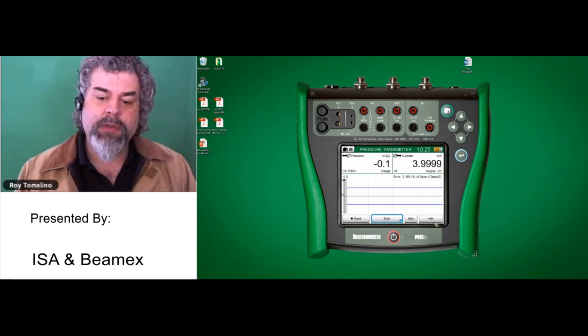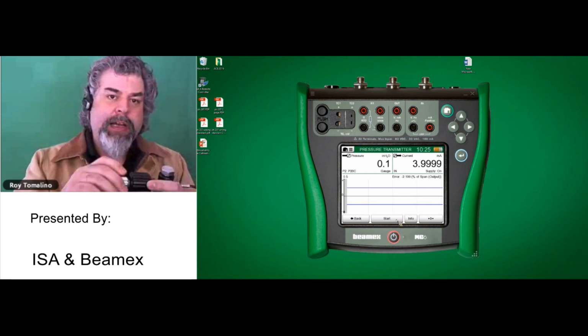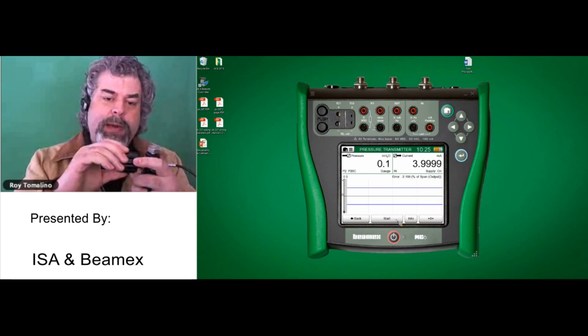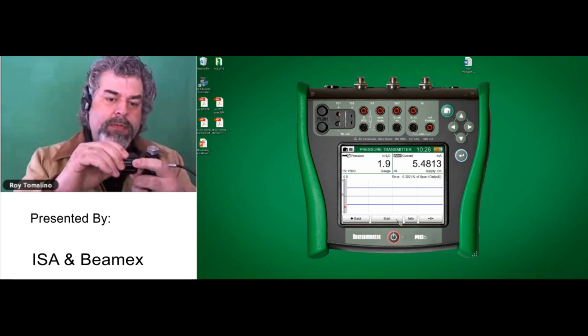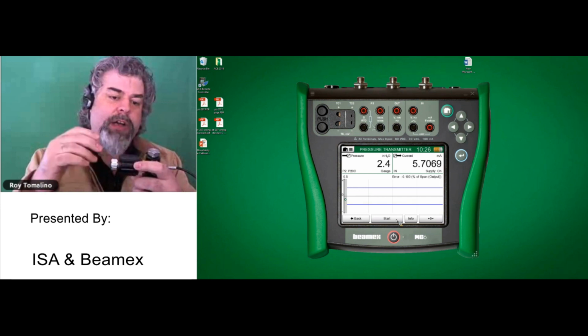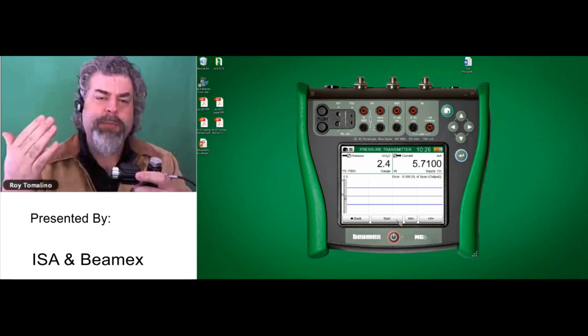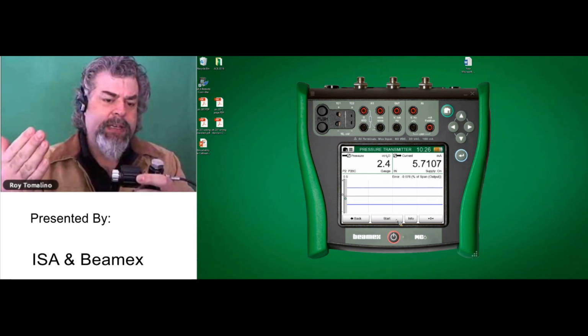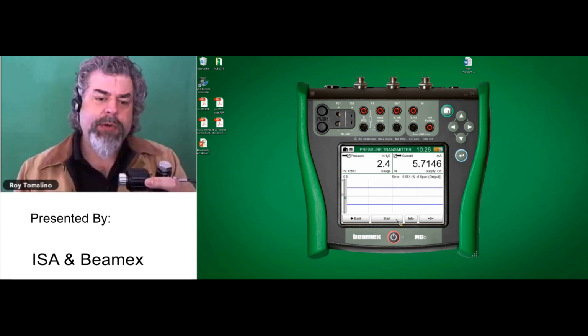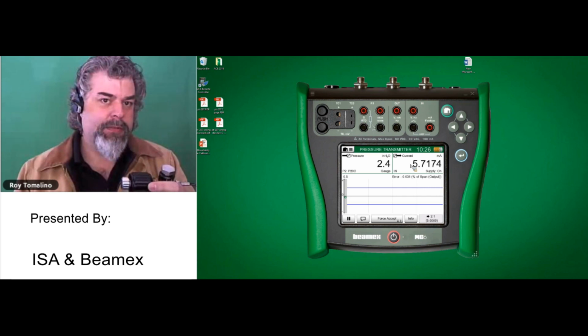First, let me zero out my transducer. And before I hit start, I'm going to use my fine-tune knob and get me up to about 1%. So this is a 207-inch of water transmitter. And I'll get us around 1%. 1% would be 2.07, and I can go a little bit higher. Notice that at 1% input, we have 10% output. So that's the definition of a square root transmitter.